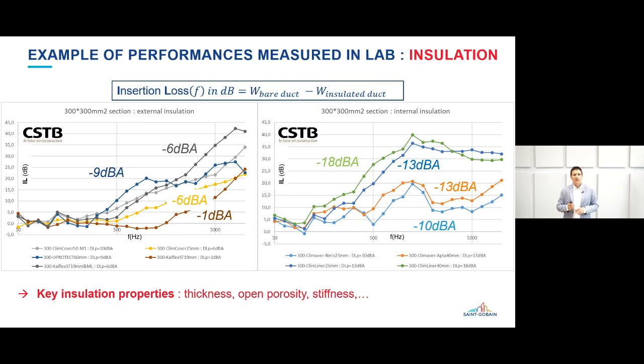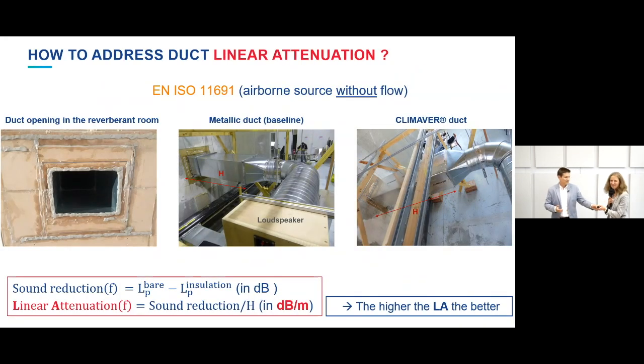Thank you, Guillermo. Regarding linear attenuation, this deals with sound absorption. We also did tests following EN ISO 11691, done with a loudspeaker and without flow. We measured the linear attenuation in bare metallic ducts and in ducts with insulation, or with CLIMAVER self-supporting duct instead of a metallic duct, and calculated the sound reduction. In the end, the higher the linear attenuation, the better the sound reduction.